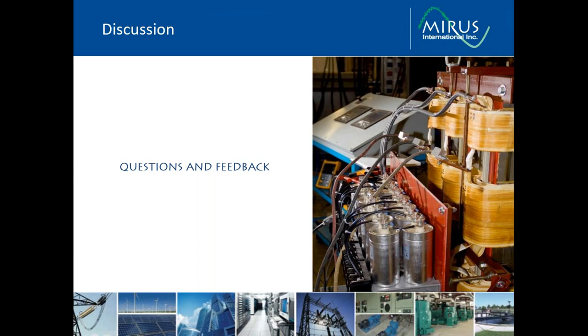The next question is, do you derate for high altitude beyond 1,000 meters? Okay, there is a derating factor. We have a version of our filter that is called an extreme duty model. That extreme duty model is designed to handle much higher background voltage distortion environments, much higher ambient temperature environments, and the elevation requirements when you go up in elevation.